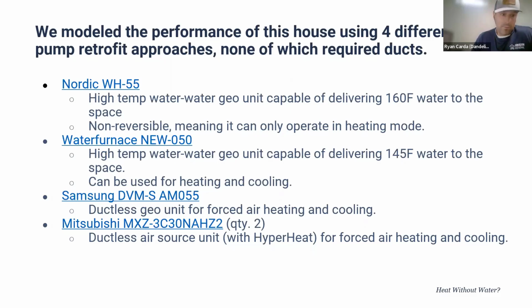We also modeled the performance of a water furnace high temp unit capable of delivering 145, which doesn't get us quite all the way there with the existing radiators, but pretty close. The nice thing about this unit is it's reversible, so you could find a way to deliver heating and cooling to the space, so long as you figured out the chilled water solution to some sort of forced air component, like a fan coil. The last 2 products we looked at, knowing we couldn't easily install ductwork throughout the entire home to serve it with one unit, were ductless products.